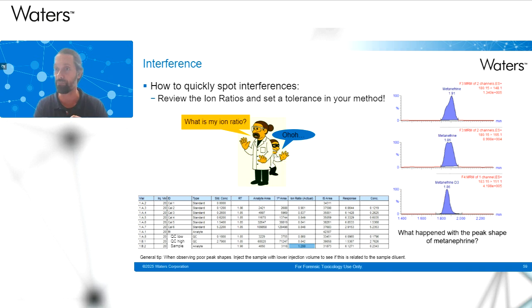And then typically we use one of those MRMs for the full quantitation. We call that a quantifier. And the other one we use as a qualifier. And then we just look at the ratio between those 2 peaks. And no matter what the concentration is, it should be a rock stable value. Unless there is this interference present. And then that should typically reveal a deviating ion ratio. Because your matrix will probably not show the same fragmentation ratio compared to your analyte.